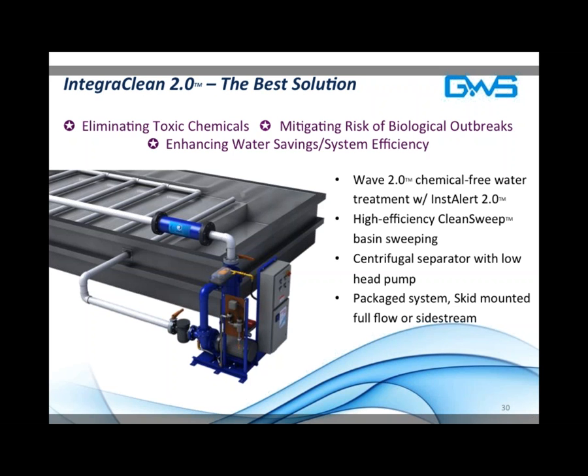Chemical service partners will do that oftentimes once every 6 months, sometimes a bit more often. Sometimes they'll use dip slides, which is a simplified version of that test, on a monthly basis, and they're highly subjective, because you're counting little circles of cultures on an agar dip slide, for example. The best way to discern whether there's biofilm in a system, especially in a cooling tower basin where you can access the system, is literally by feel. So if you feel in your cooling tower basin and it's a slimy, slippery surface, that is biofilm. It's the same type of feeling that you would note if you felt the inside of a pet's water dish, for example.